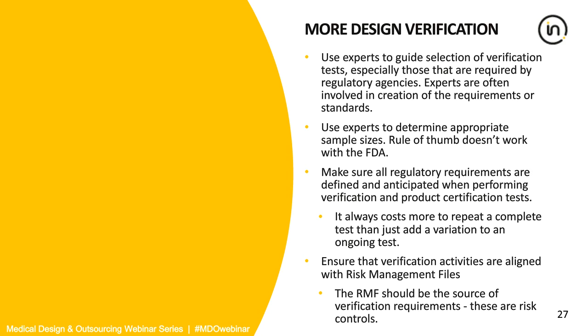And then ensure that your verification activities are aligned with your risk management files. Your risk management file really should be the source of the verification activities. Mitigation of risk is often achieved by evidence that you meet the specifications. And that's what the verification testing does. So make sure it's aligned. People fail with electrical testing often at the very start because they don't have a risk management file that identifies all the potential hazards that are actually in the electrical safety standards, in which case we have to send them back and they do the risk management file again. And the same can be said for almost any verification activity.